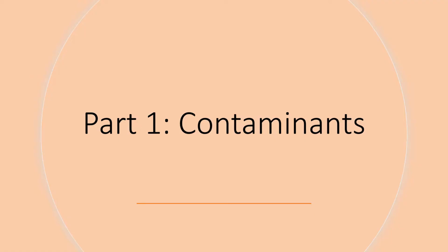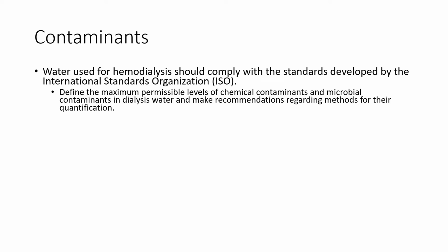Let's begin by discussing water contaminants in general. Water used for hemodialysis should comply with the standards developed by the International Standards Organization, or the ISO, and adopted by many national agencies worldwide.